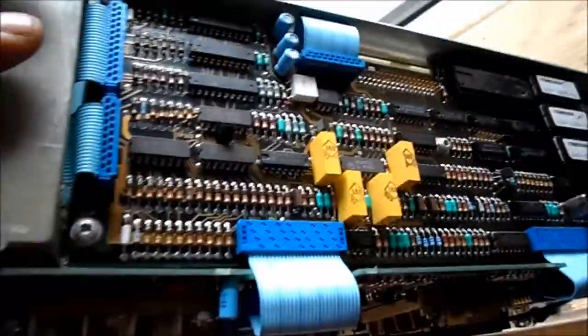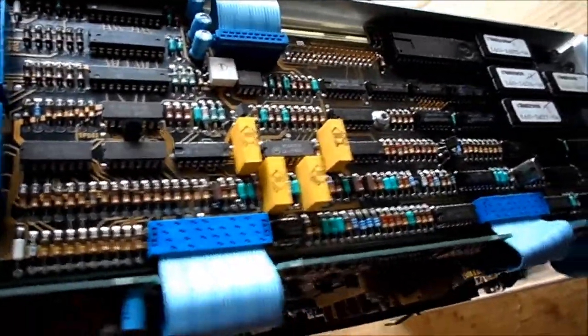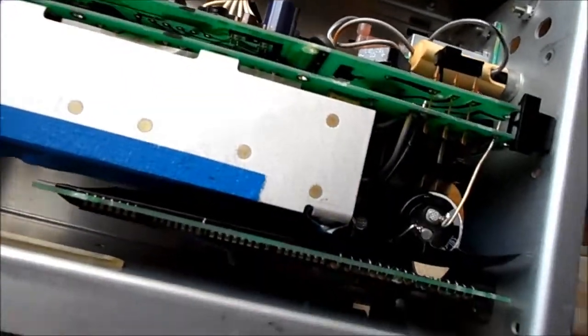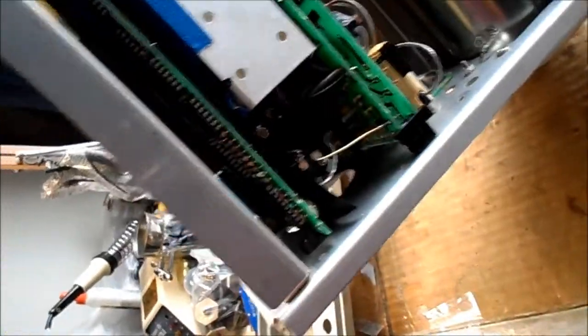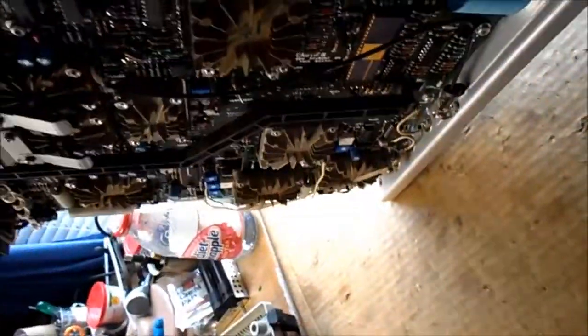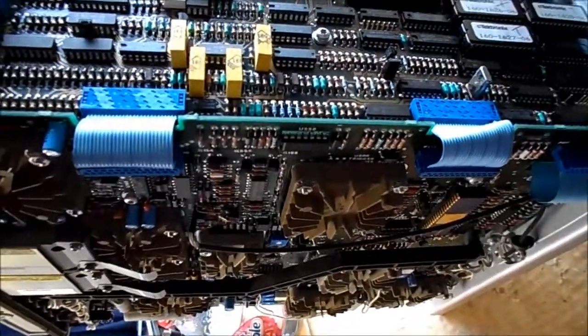What I had to do to get the scope running, having no idea what the problem was, is I did rebuild the power supply to the best of my ability at the time. The trouble of why it's not put back together is due to the fact that those capacitors there, the power capacitors on this power supply board, are physically too big to fit so I can't put the fan and the shroud back in for the fan.